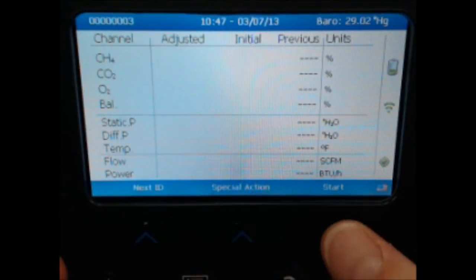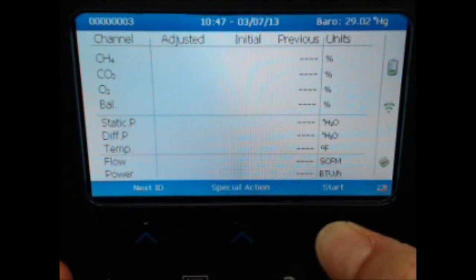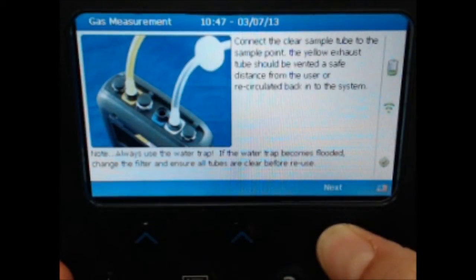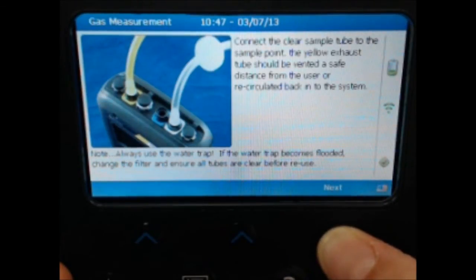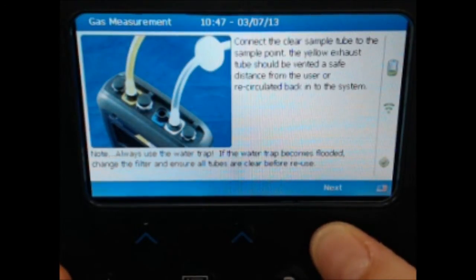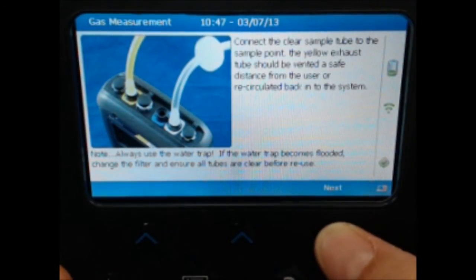After the clean air purge is complete, select the Start function to start the reading process. Connect the tubes to the top of the instrument following the instructions on the screen. The clear hose should connect to the white port, the blue hose should connect to the blue port, and the yellow exhaust hose should connect to the yellow port. Select next to continue.